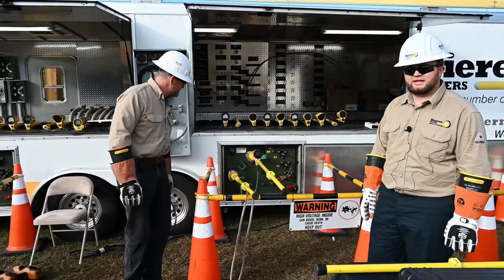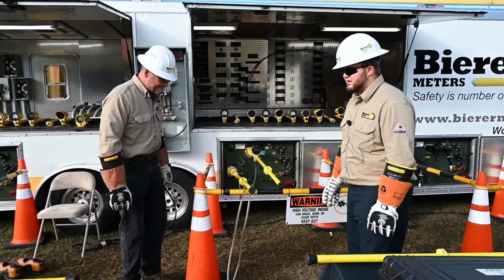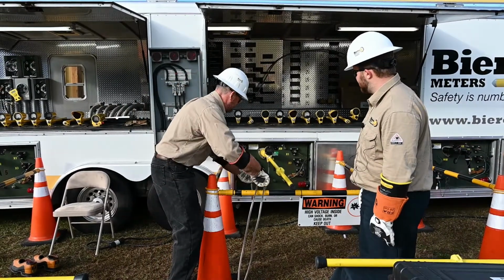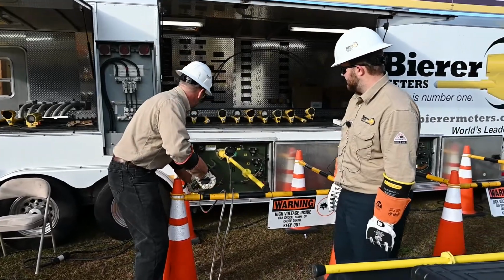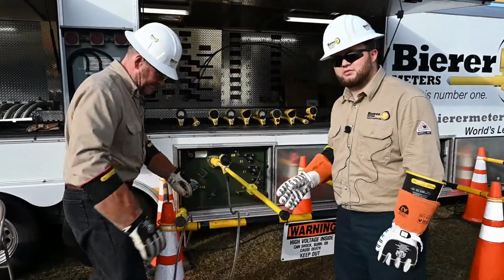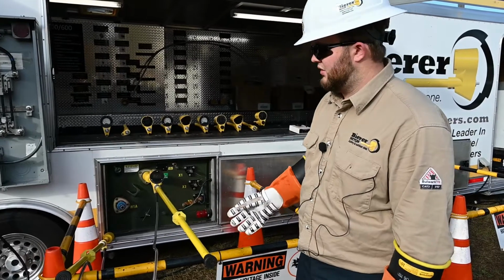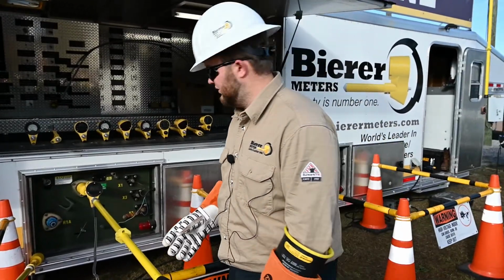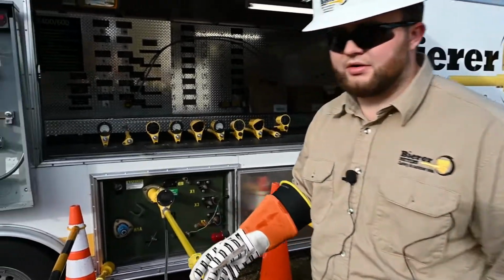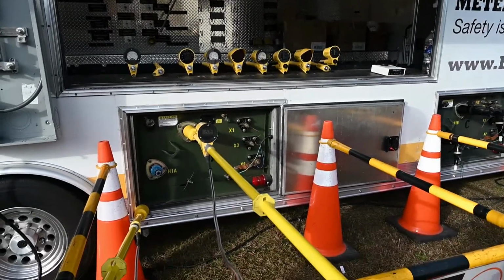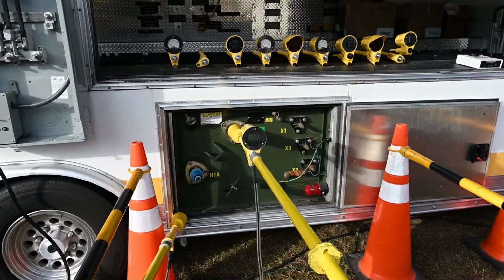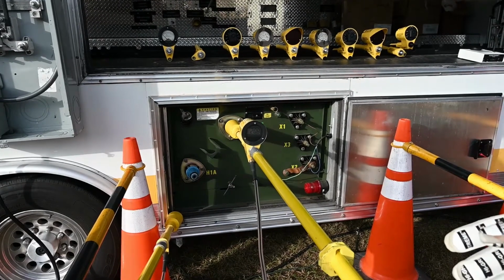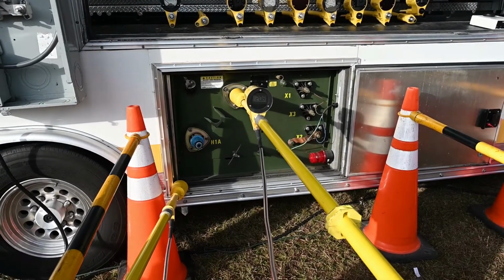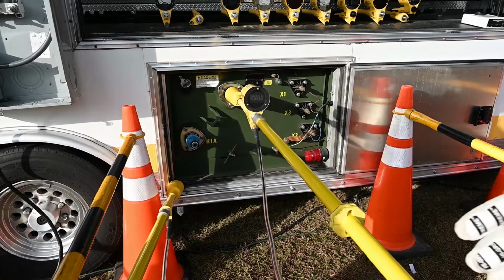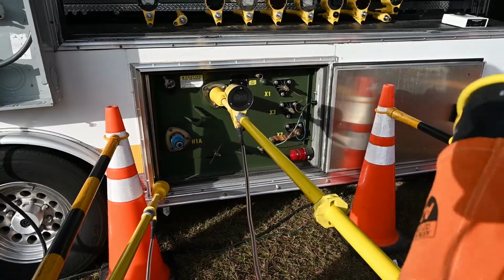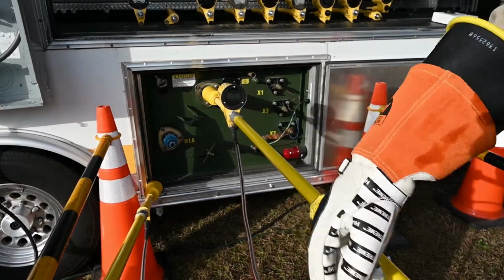So there's a little bit of bleed in the cable. There's nothing wrong with it. It's just going to bleed off to the ground a little bit there. Anytime you're using a corded tool to read voltage to phase, or especially if you're high potting with a corded tool, you want to take the second probe to ground first. The reason is to, one, bleed off the capacitance if you're charging the cable to high pot, or two, if you're taking voltage or phasing, bleed off any capacitance between the two meter probes and the cord.